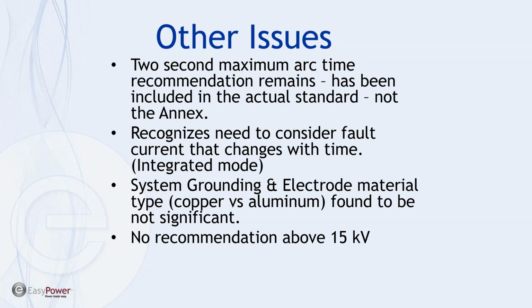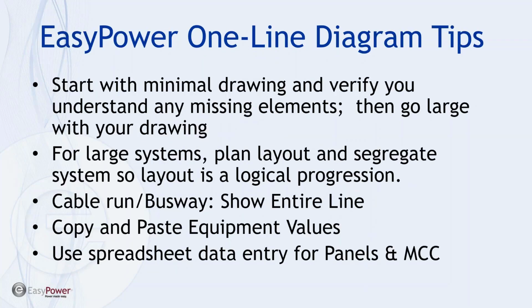Now, in terms of other changes in the standard, the 2-second maximum, what some people refer to as the 2-second rule, has been included and is pretty much verbatim. The fact is it was in an annex once before, and now it's part of the main body. So it recognizes the potential, if we have high incident energy due to long trip times on protective devices, and it's reasonable that an operator or technician could remove themselves from the area if a fault occurred, that 2 seconds might be the maximum calculation time, or the limit on doing the calculations for incident energy, if our operator could remove themselves within that 2 seconds.